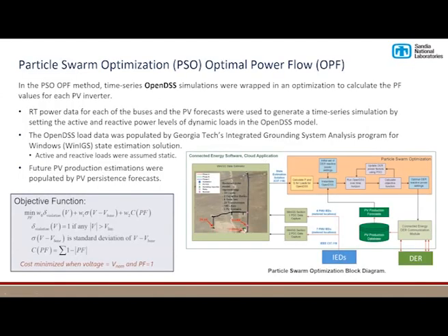The last technique is based on a particle swarm optimization technique using an OPF, optimal power flow, where we measure from the power system and a bunch of intelligent electronic devices like PMUs, micro PMUs, and the inverters themselves. Different data is passed to a Georgia Tech state estimation tool called WinIGS. It calculates the current states. We export that into a particle swarm optimization routine that instantiates a bunch of power factors for the different DER devices, and then runs the optimization to calculate the optimal power settings based on an OpenDSS simulation running here. Those power factor settings are then communicated down to the end devices.